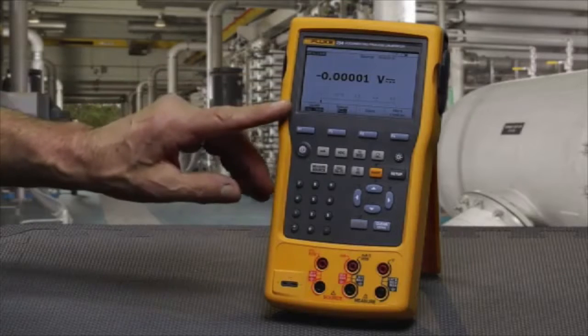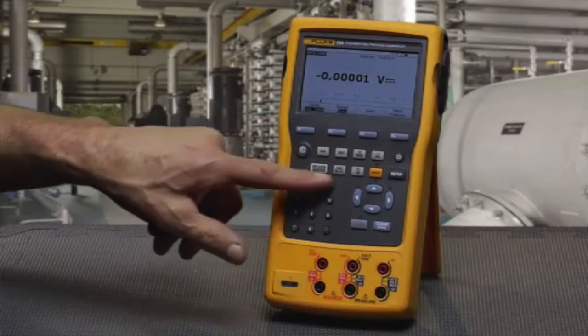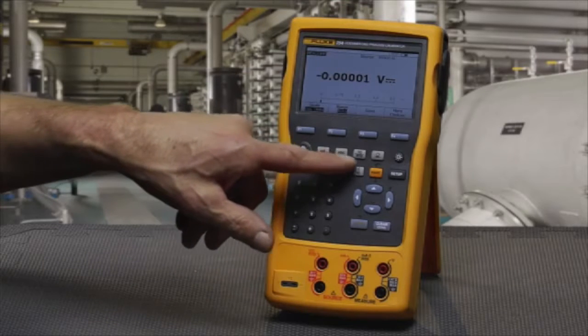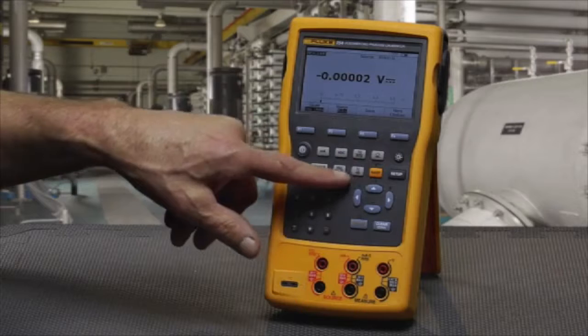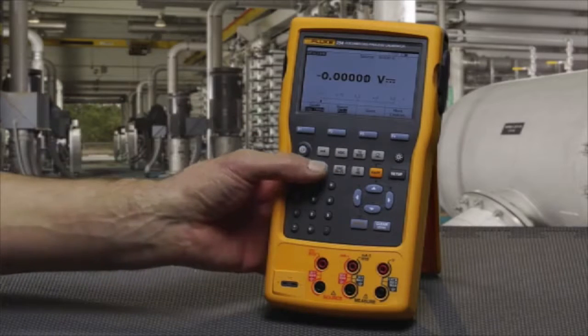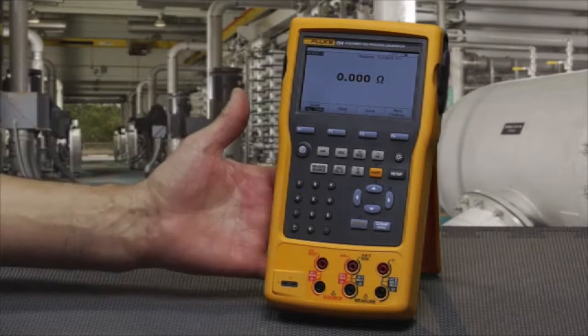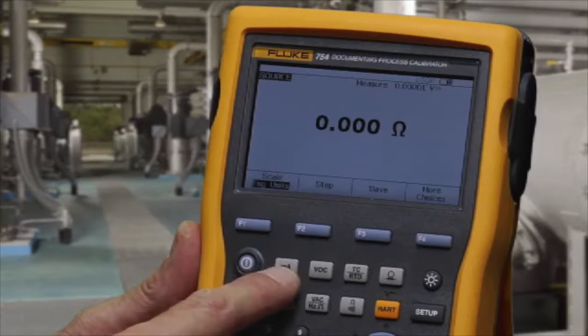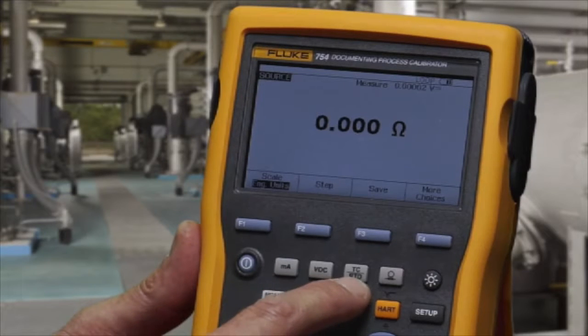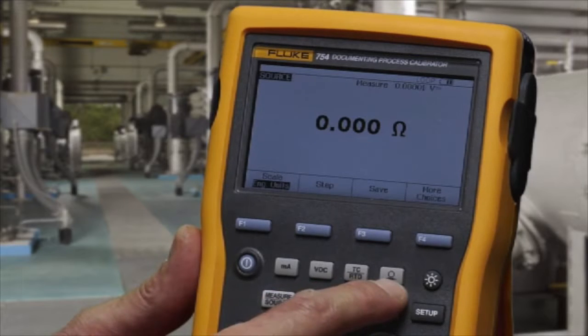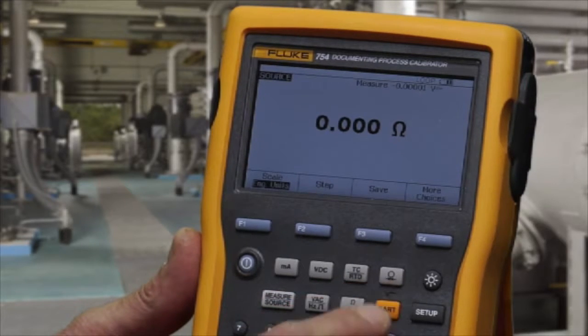With the measure screen, you would select the function that you'd want to measure: volts DC, milliamps, thermocouples or RTD, resistance or volts AC. In the source screen, you'd configure what you want to source. And we can source milliamps, volts DC, we can simulate thermocouples or RTDs, we can measure pressure being sourced to a device we're testing, we can source frequency, and simulate resistance.